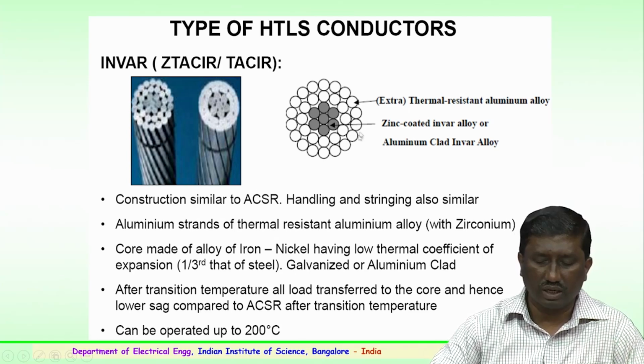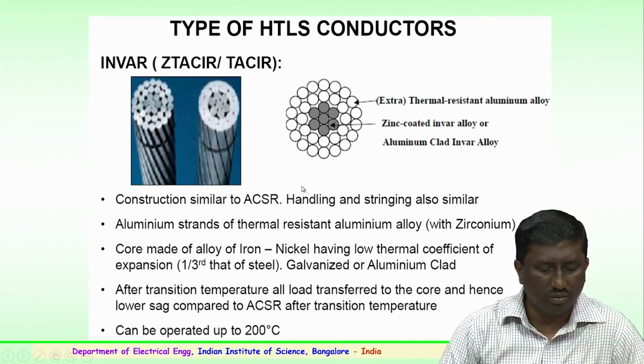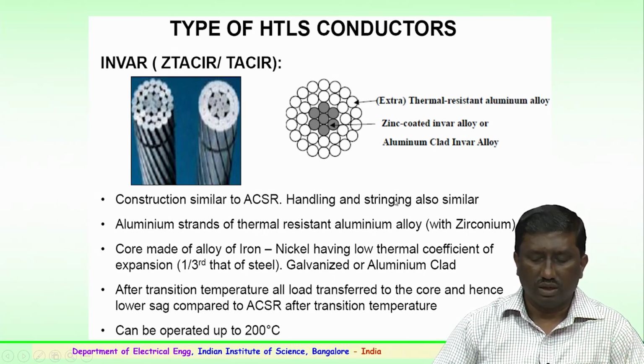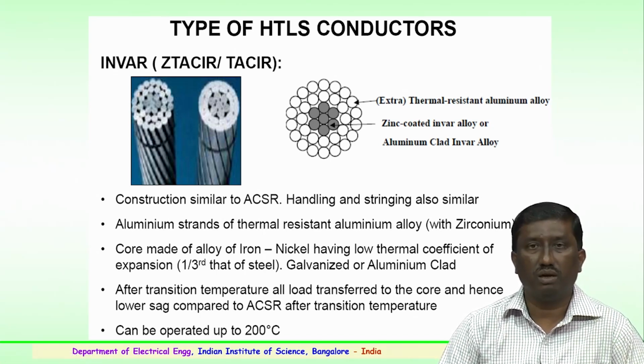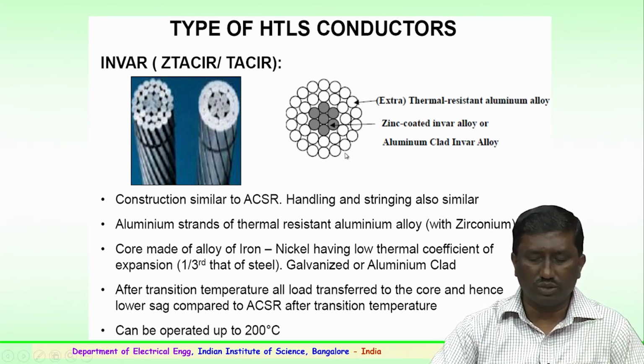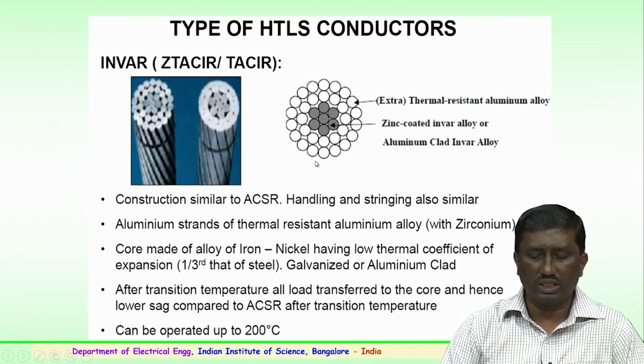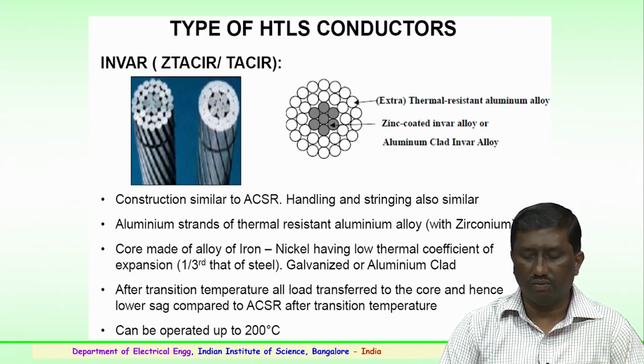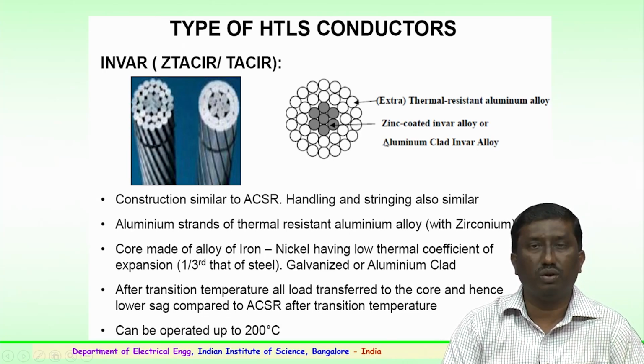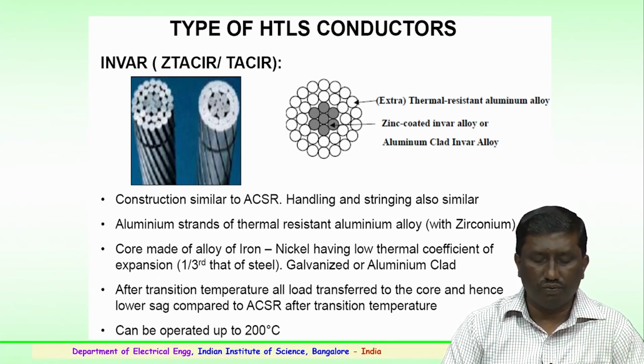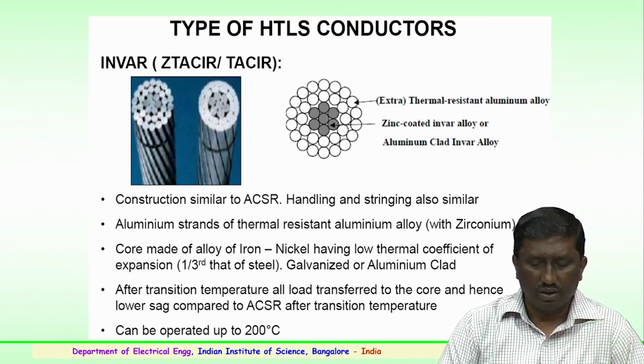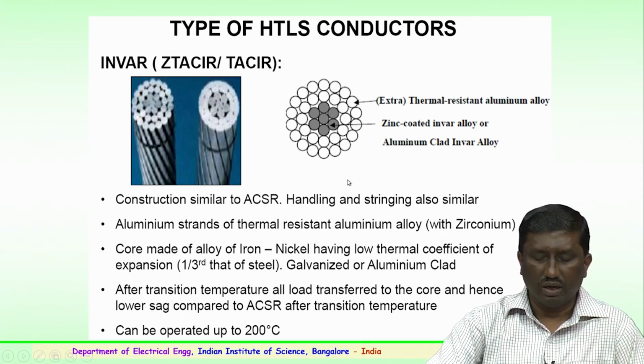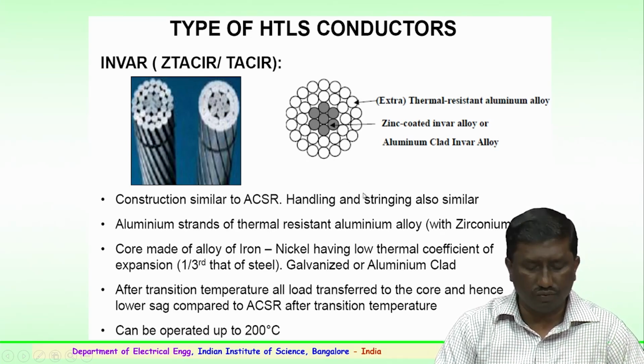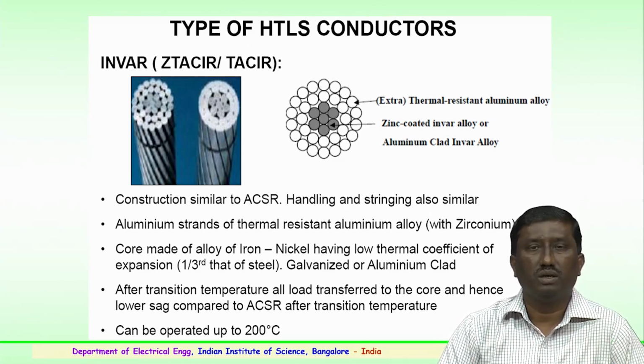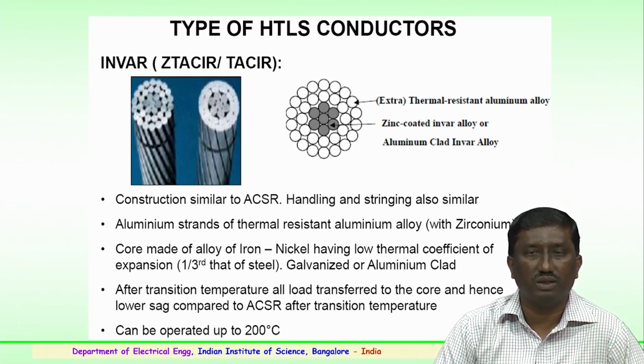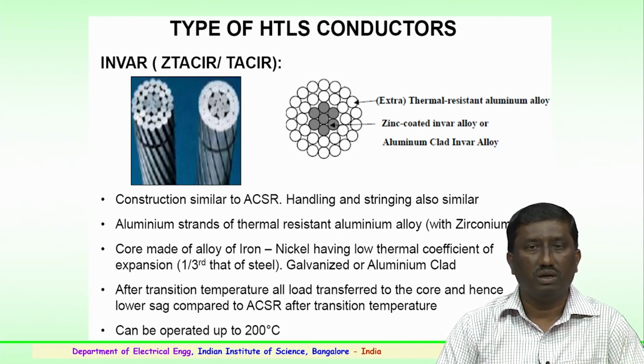Here the construction of this conductor is similar to the aluminum conductor steel reinforced conductor, and handling and stringing are also similar on the tower. So, you can see the aluminum strands, which are thermal resistant and made of an aluminum alloy with zirconium added into the aluminum alloy. The core consists of an alloy of iron and nickel, which has a low thermal coefficient of expansion. This is supposed to be 1/3 that of steel. So, it is lesser by 1/3 in comparison to the steel.